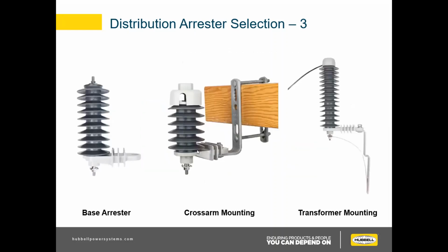So now we'll go on to hardware configurations. On the left here, this is our base, most commonly sold part number. It's just the arrestor, no cap, no lead wires, on an insulating bracket. So pretty simple, straightforward. Next, we have a little more specialized one, with a cross arm bracket and a wildlife cap. And then on the far right, we have a wildlife cap with a lead wire going to the line side, and then a transformer ground strap with a transformer mounting bracket.